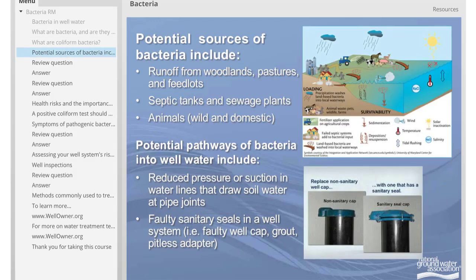Potential sources of bacteria include runoff from woodlands, pastures, and feedlots, septic tanks and sewage plants, and wild and domestic animals. Potential pathways of bacteria into well water include reduced pressure or suction in water lines that draw soil water at pipe joints, faulty sanitary seals in a well system such as a faulty well cap, grout, or pitless adapter.